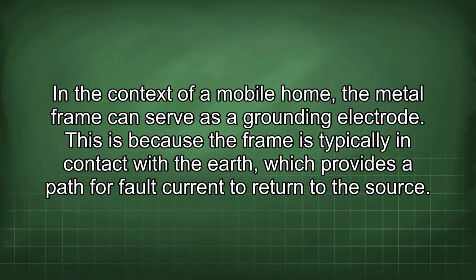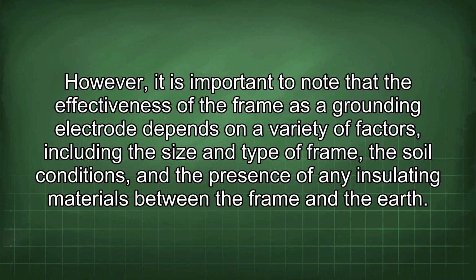In the context of a mobile home, the metal frame can serve as a grounding electrode. This is because the frame is typically in contact with the earth, which provides a path for fault current to return to the source. However, it is important to note that the effectiveness of the frame as a grounding electrode depends on a variety of factors, including the size and type of frame, the soil conditions, and the presence of any insulating materials between the frame and the earth.